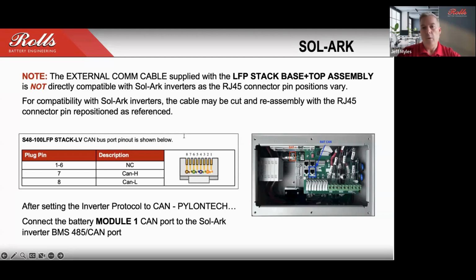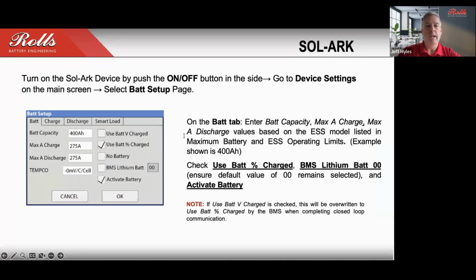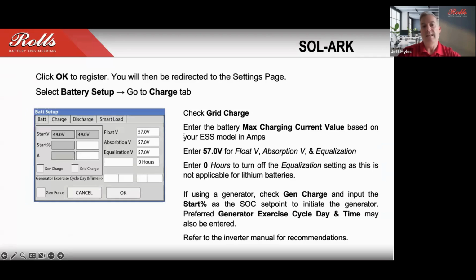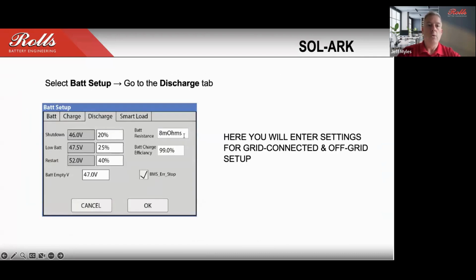So, we walked through essentially the same steps with Sol-Ark equipment, explaining what the battery type should be set at, battery percentage, and so on, and walk you through those menu options from start to finish. And then once that is done, you should have the system set up in closed loop communication. So these settings, one thing that is very important is to ensure that you're setting that shutdown, low voltage, and so on.